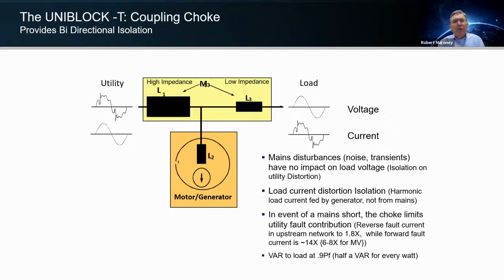Another component to the UPS that we're going to talk about here for a moment is essentially our input-output choke. It's an isolation, high impedance, and a connection choke, low impedance, that's connected to the motor generator. Now, the choke actually provides us a connection point to the critical path of the UPS. It allows us to inject or take VARs off of the critical path to hold output waveform to plus or minus 1% at all times. It also provides true isolation input to output.